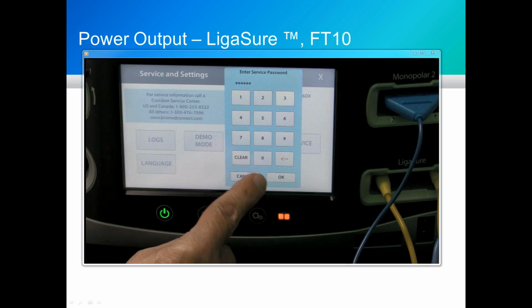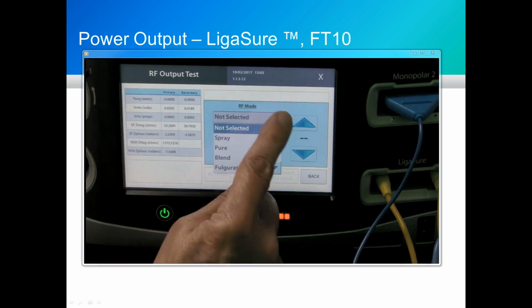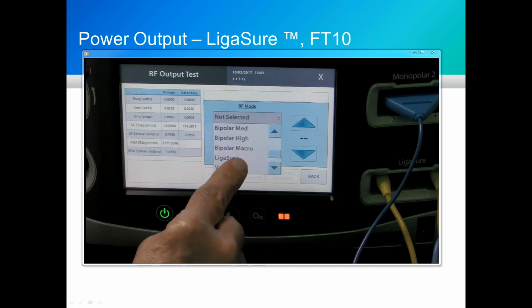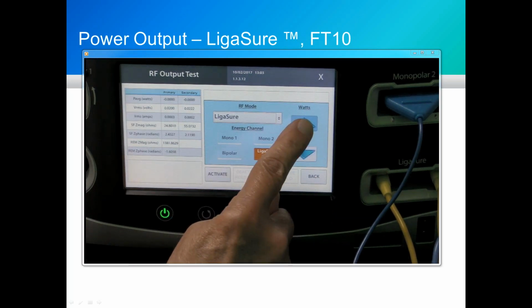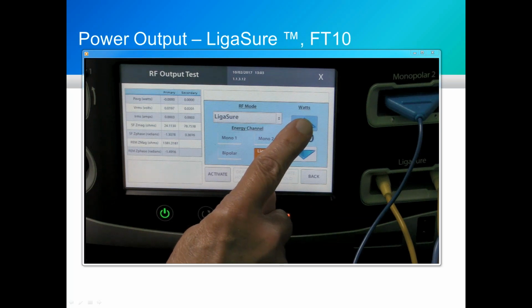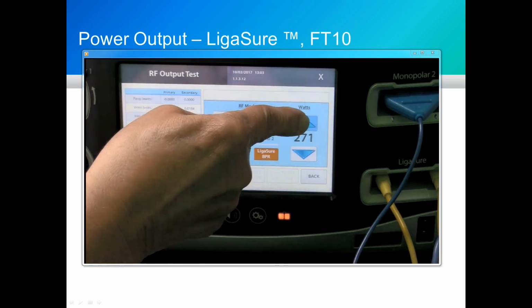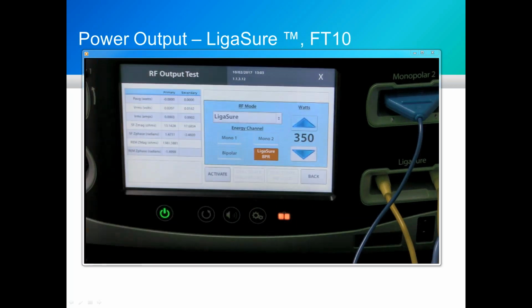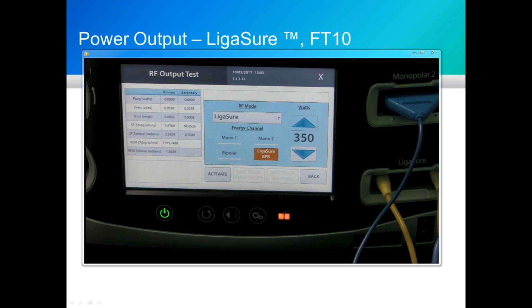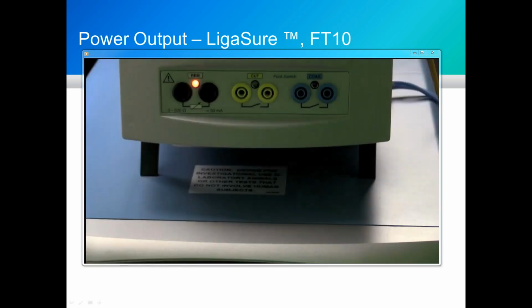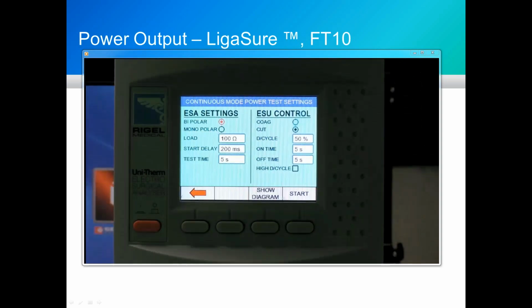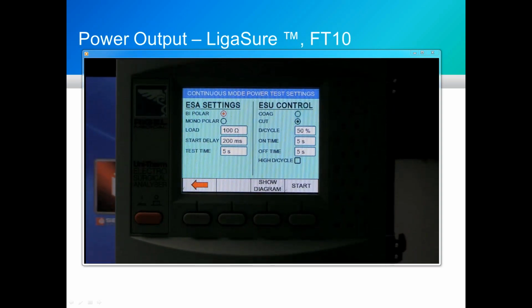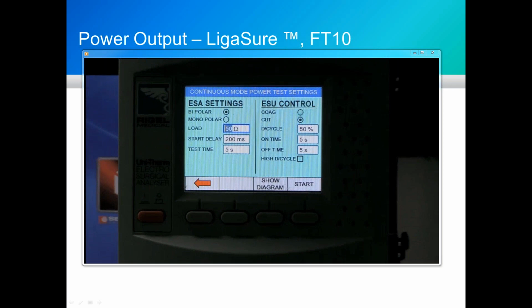I'm entering in the password to go into service mode. I'm going to come down and I'm going to select LigaSure for my energy port. I'm dialing in maximum power. If you had the old connector that extended those cables with the 2 little fixed dots on them, that would not be recognized any longer by the unit because there's no scanner looking at dots. For LigaSure testing, I select a value for my load of 50 ohms.